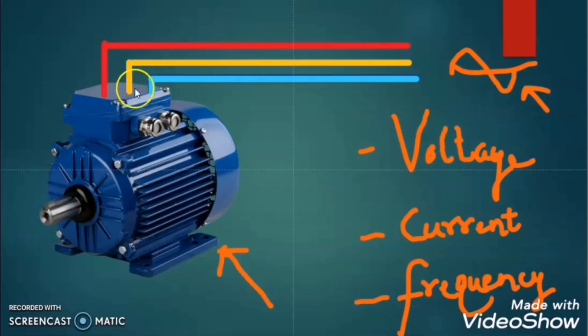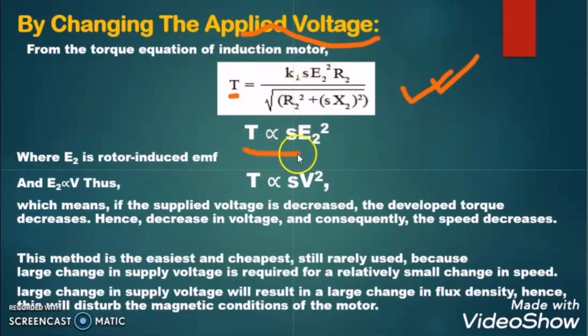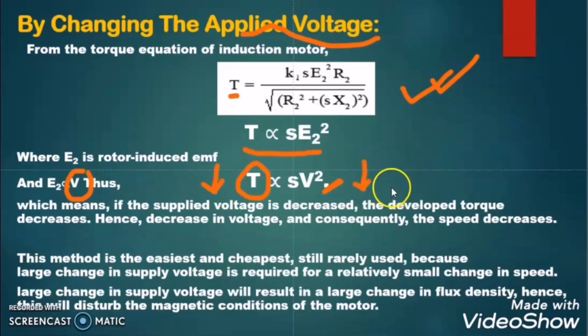Let us first change the power supply voltage to the induction motor and analyze what is happening with the speed. As we know, the torque of the induction motor is equal to K1 × S × E2² × R2, divided by R2² + S × X2². The torque is directly proportional to the induced EMF in the rotor, and the induced EMF is directly proportional to the applied voltage. So the torque is directly proportional to voltage squared. If we decrease the voltage, we decrease the torque, and as the rotating force reduces, the speed of the motor will reduce.